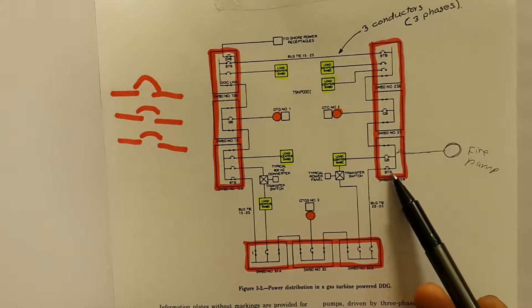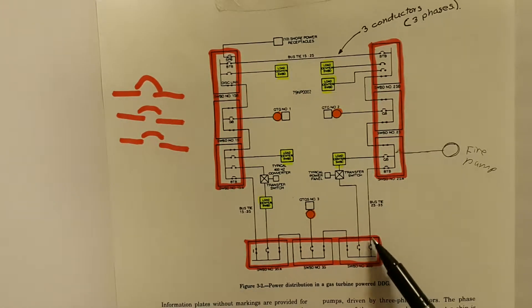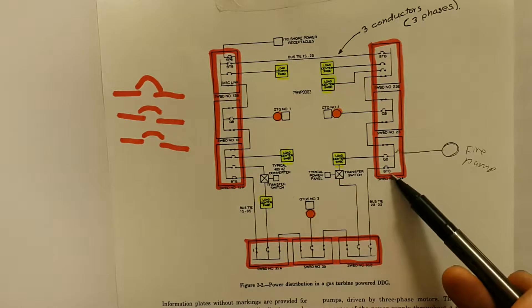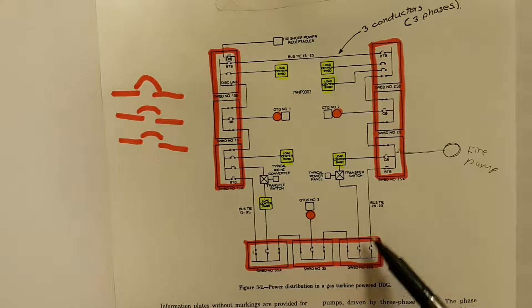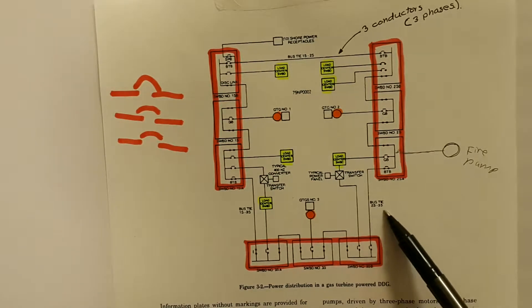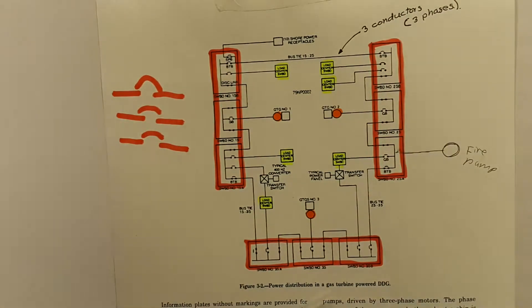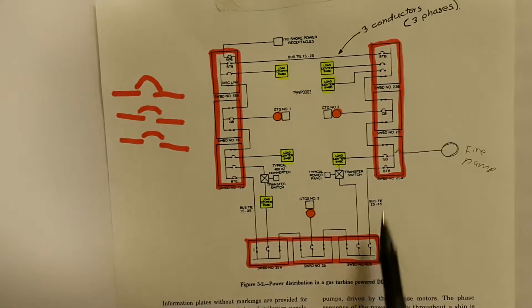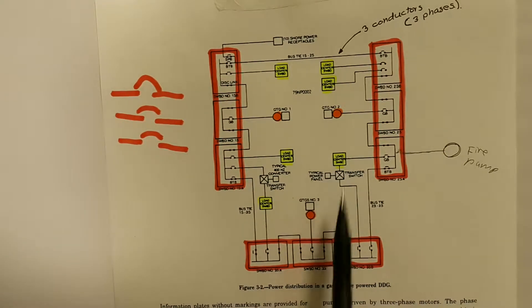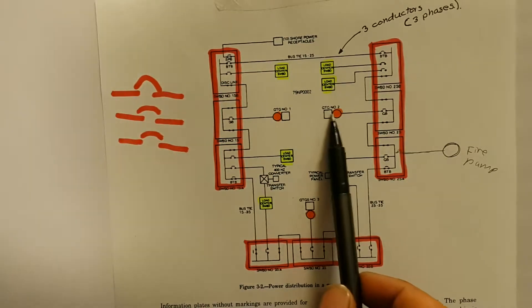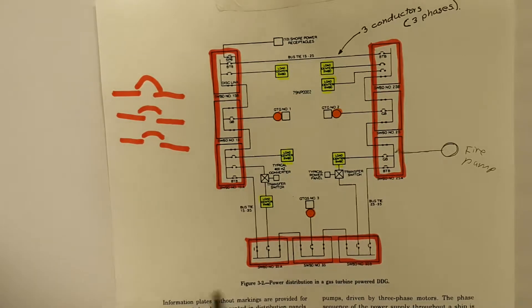This over here, I got a bus tie breaker because this line represents a bus tie. A bus tie is a set of wires or conductors that connect two switchboards. So this bus tie is called 2S, 3S because it connects number two switchboard to number three switchboard. If these two bus tie breakers are closed, it will allow us to power number three switchboard all the way from number two switchboard.